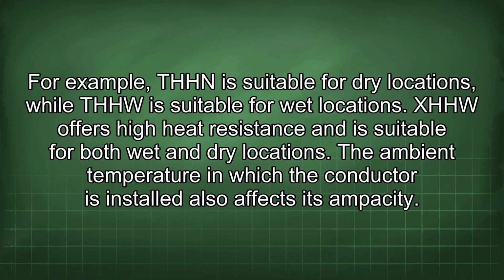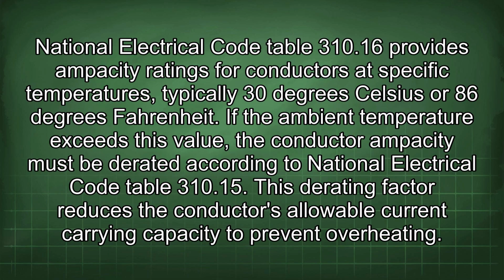The ambient temperature in which the conductor is installed also affects its ampacity. National Electrical Code Table 310.16 provides ampacity ratings for conductors at specific temperatures, typically 30 degrees Celsius or 86 degrees Fahrenheit. If the ambient temperature exceeds this value, the conductor ampacity must be derated according to National Electrical Code Table 310.15. This derating factor reduces the conductor's allowable current carrying capacity to prevent overheating.